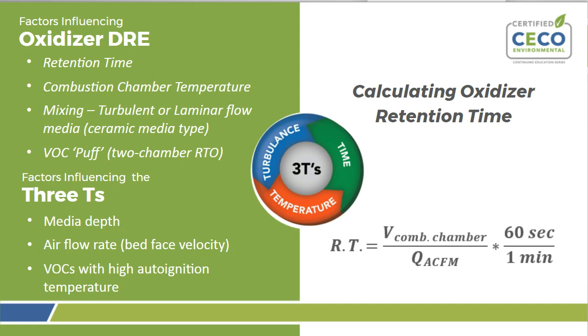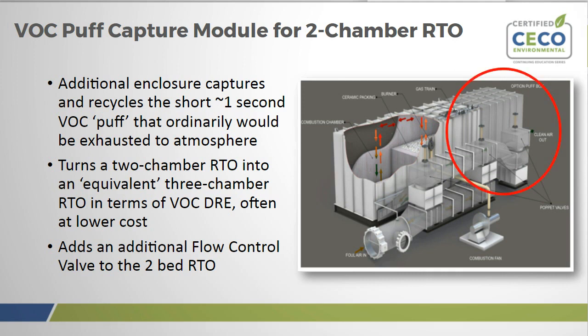Now talking a little bit more about that VOC puff. I think I mentioned the puff capture module for a 2-chamber effectively makes a 2-chamber act similarly to a 3-chamber or 5-chamber with a purge bed, but you don't need an entire new bed for the RTO. So it's this additional enclosure, there we go, that red circle. That additional box in the back with the additional poppet valve captures that 1 second of VOC puff. Generally, it's sized to capture a few seconds to ensure 100% capture efficiency. But it then reroutes that VOC puff back to the inlet of the unit during that cycle where it's oxidized.